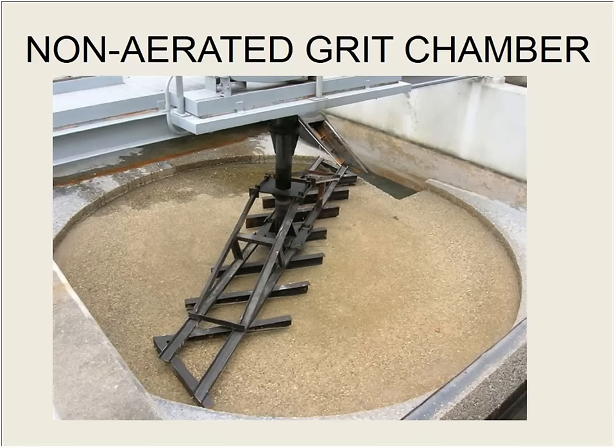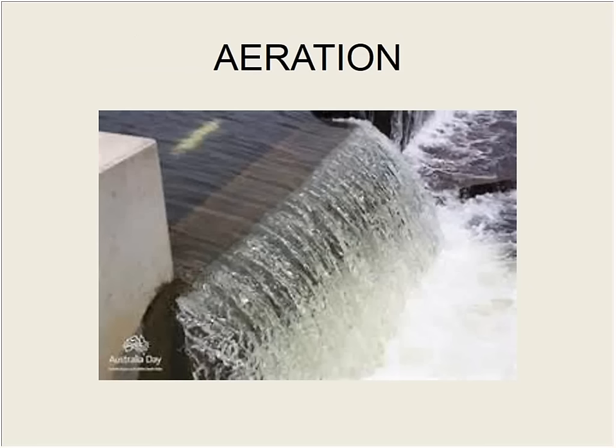Thing about it is, this could be Amherst, Mass. They've got a system like this. The material comes in, goes through their flow meters, goes directly into this. Again, it's old wastewater, so it can be rather odorous. So one way that we try to do, no matter what our system is, we want to get some oxygen back in this water so we shut down any kind of anaerobic operation or even some of the facultative. The ones that are non-aerated grit chambers tend to have a drop afterwards. It's going to flow over a dam, drop a couple of feet. That's just enough to aerate that very well, get it back up, and shut down any anaerobic activity.